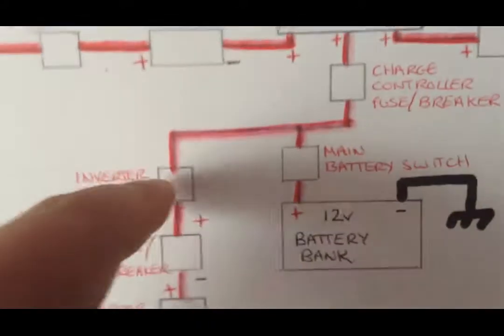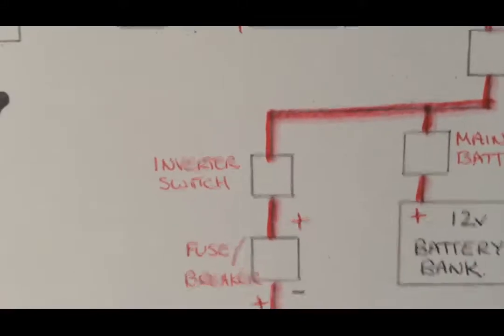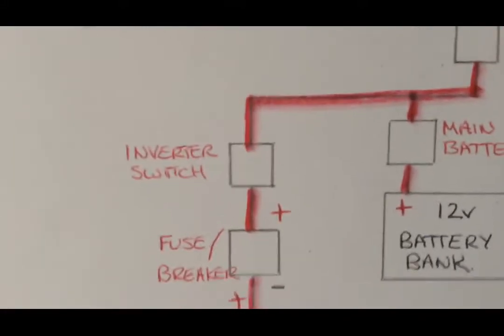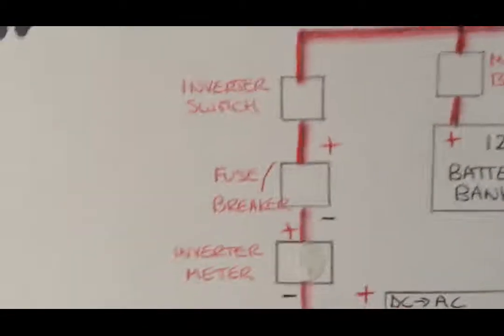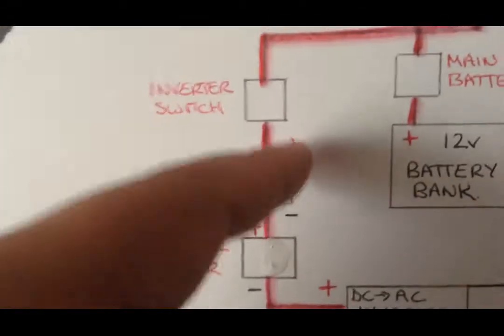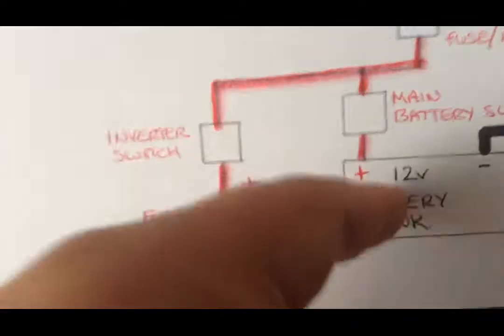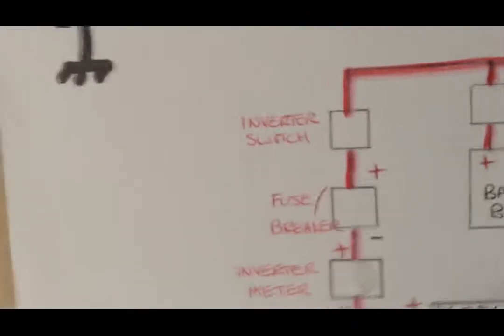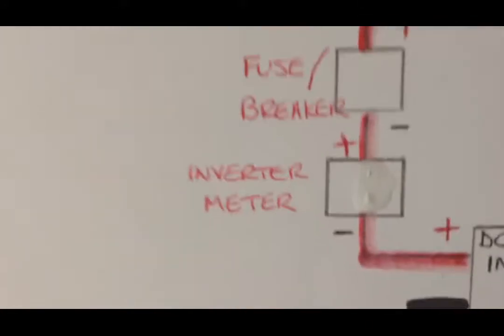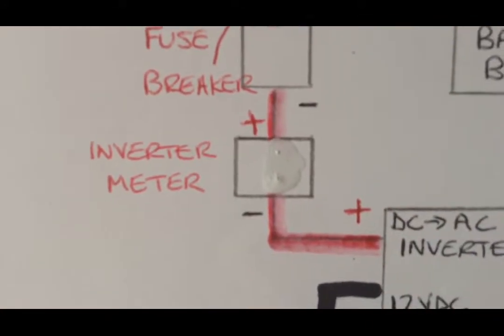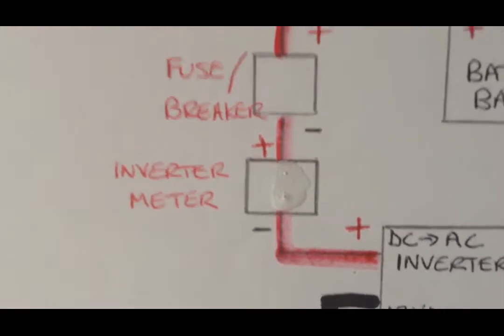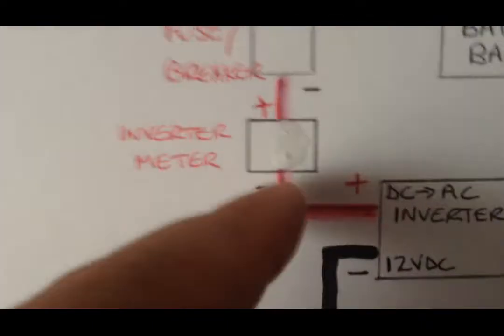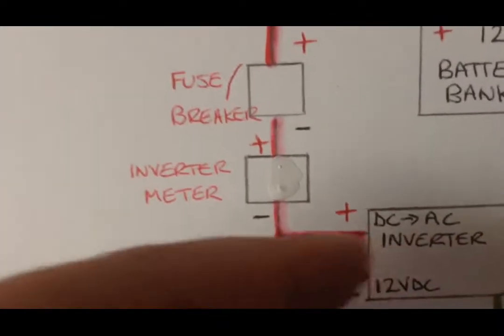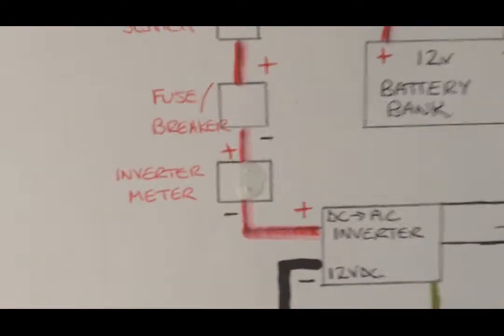This switch would turn your inverter on and off. Then you go to a fuse or breaker - again, if using a breaker, the plus side goes towards the plus terminal of the battery bank. From the fuse or breaker, we go to an inverter meter, since the gentleman wanted to know how much current his inverter was drawing. The plus of the meter faces towards the battery bank, and the minus of the meter goes to the plus input of the inverter. I'll just take you down here.